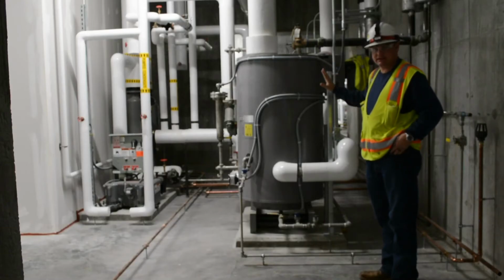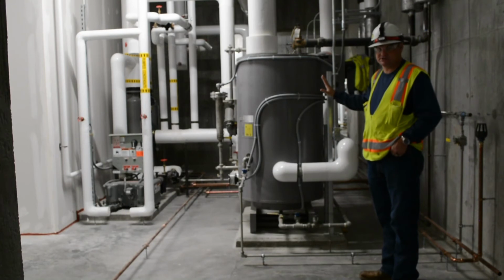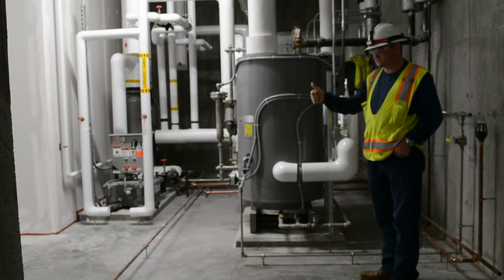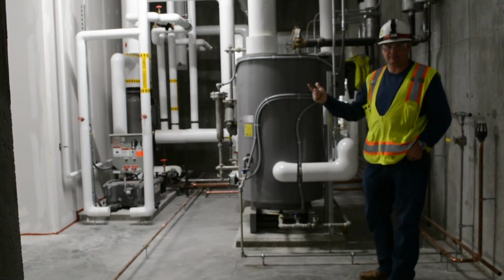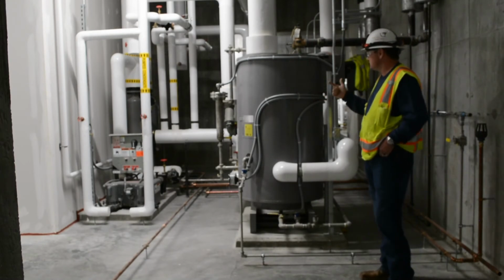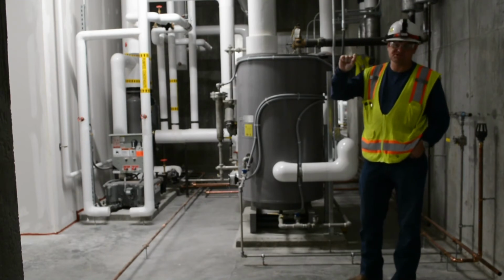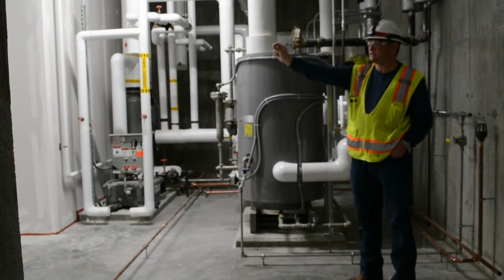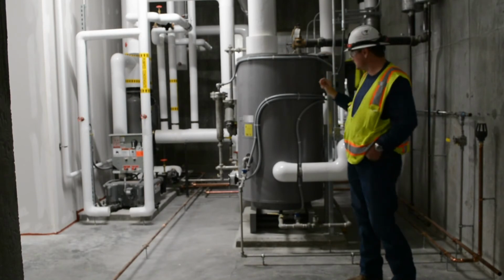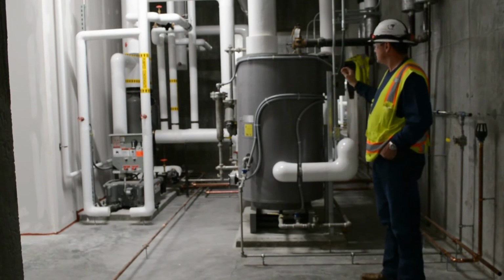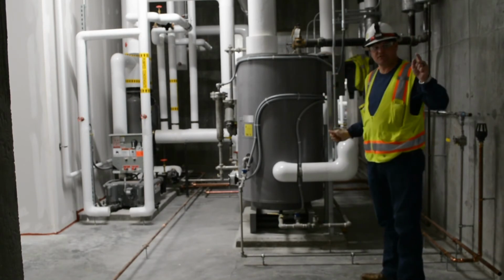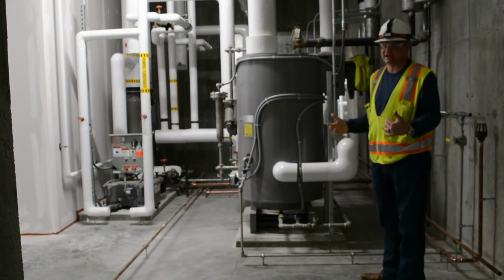This is our clean RO water steam generators for the sterile laboratories, GMP, good manufacturing practices, and the vivarium lab, or the animal lab. So we're utilizing the reverse osmosis pure water from the old existing lab to generate steam to inject into the laboratory air handlers for humidification purposes only.